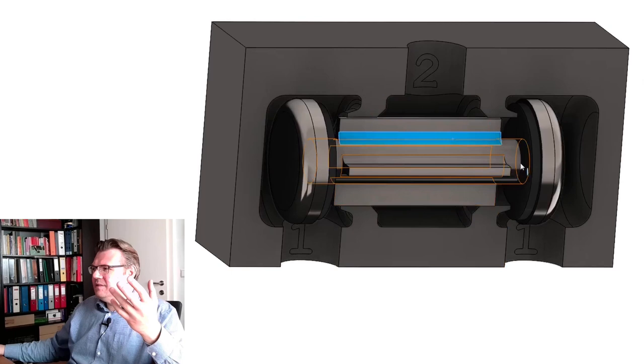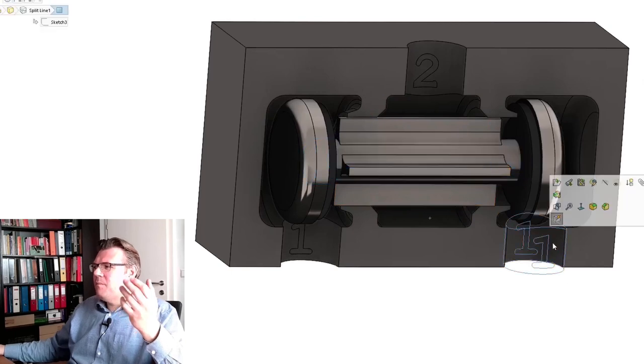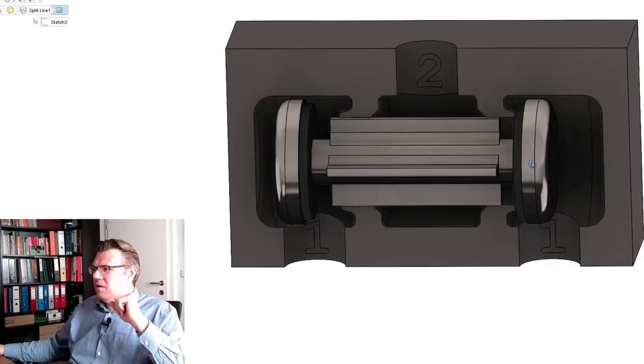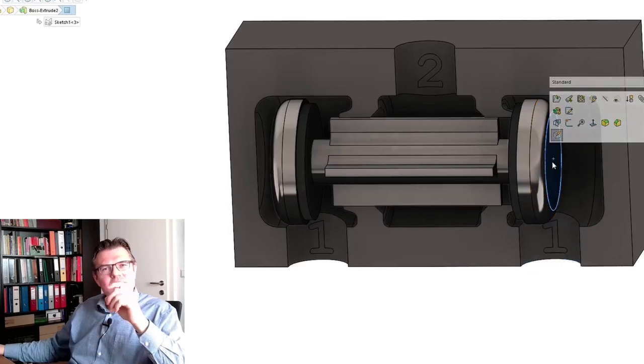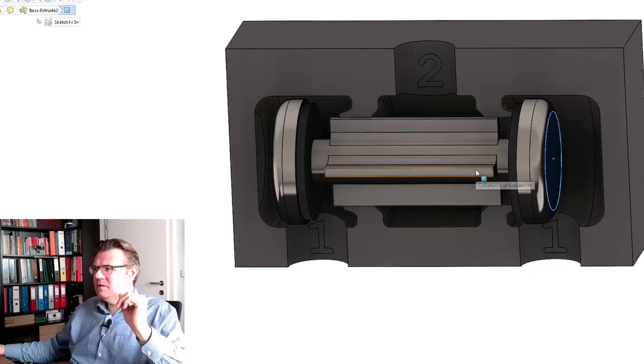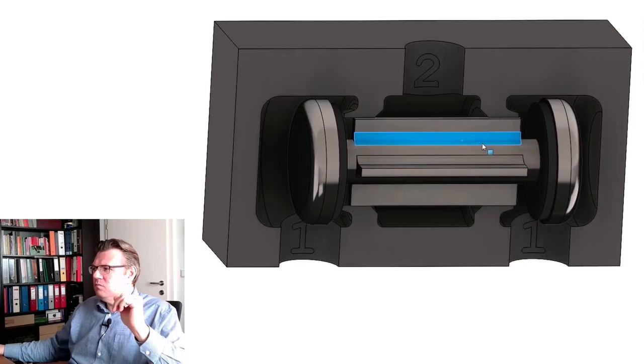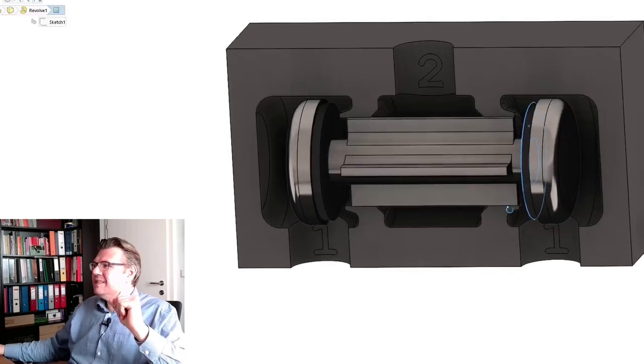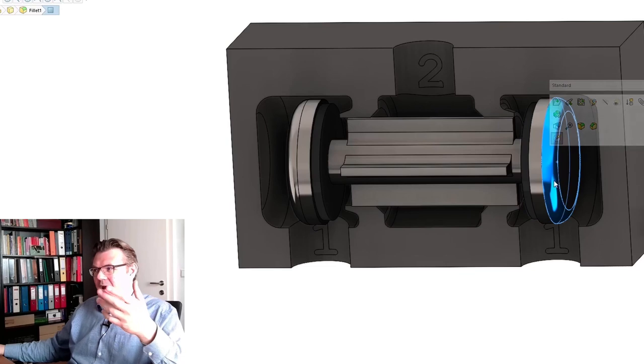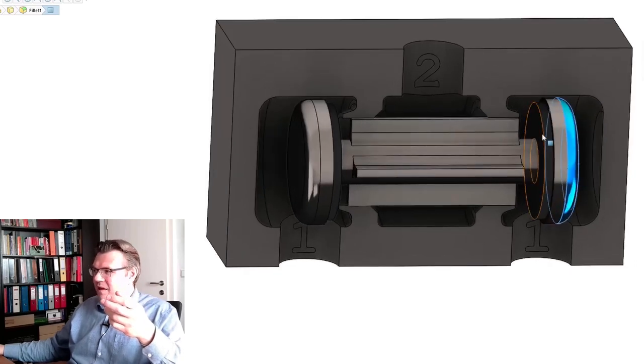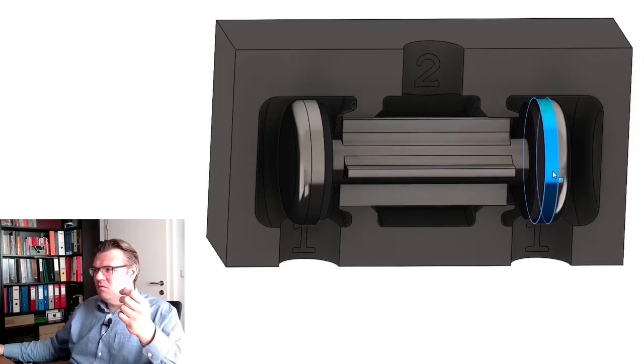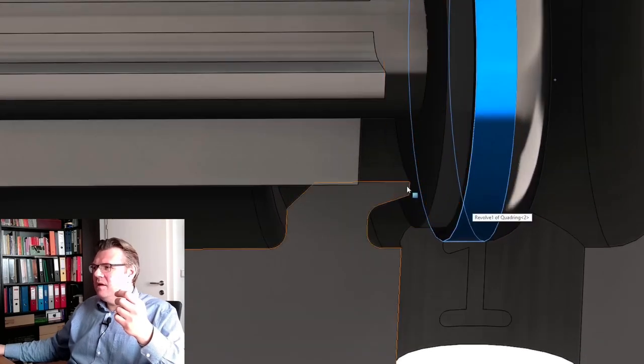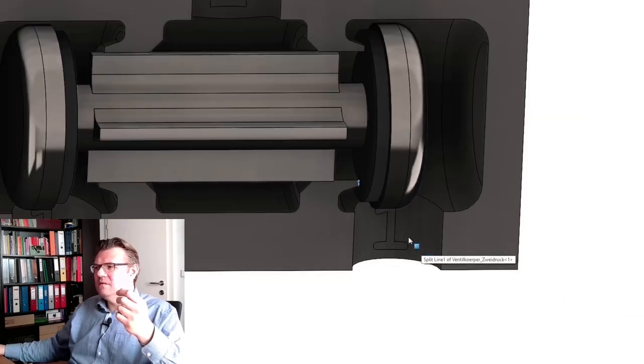How is this? If it's moved to the right, if we apply pressure here, we will apply force at this side of the piston, and also, if it's somewhere in the middle, at this side of the piston. Since this side of the piston, the right-hand side, is bigger than the left-hand side, the piston will start to move in this direction. And then here, it will be sealed.